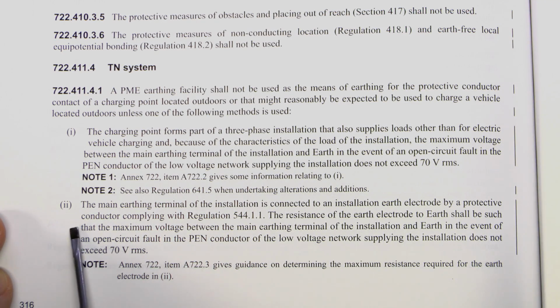The other one is the main earthing terminal in the installation is connected to an installation earth electrode by a protective conductor complying with the regulation. The resistance of the earth electrode to earth shall be such that the maximum voltage between the main earthing terminal of the installation and earth, in the event of an open circuit fault in the PEN conductor, does not exceed 70 volts.